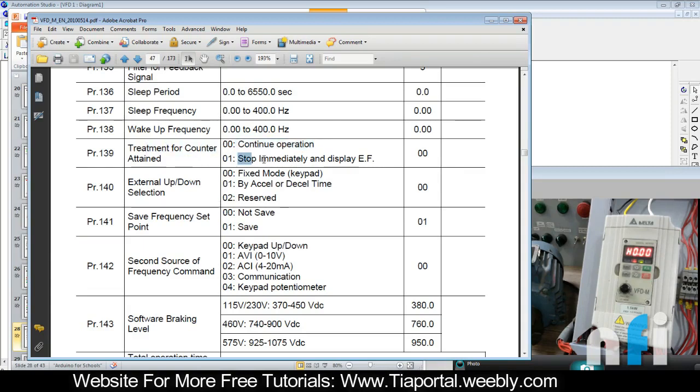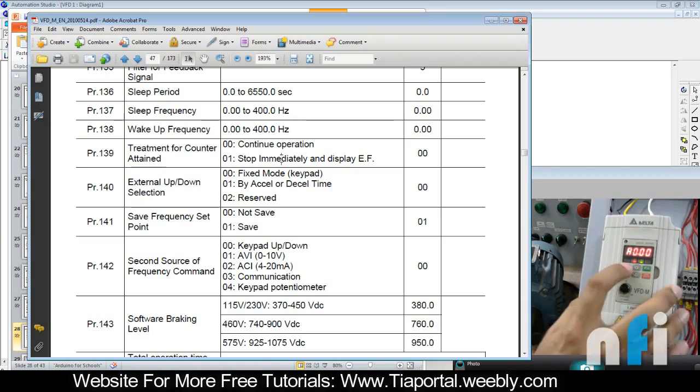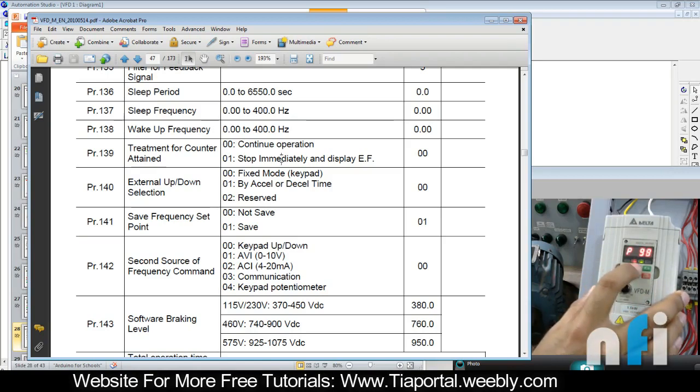If it continues operation, then it will not stop. So here let's enter 01, which will stop the drive and the counter will reset. So parameter 139, I have entered 01.